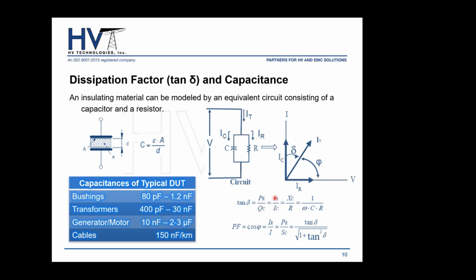Now, in power factor, basically, like I said, these values are usually very small. We're talking about, for example, in a transformer, a good transformer has 0.5% tan delta value. So we're talking about 0.005 tan delta value. So the resistive vector is usually very close to this y-axis. And so when we talk about the difference between power factor and tan delta, there really isn't a big difference. The only difference is the angle that is being chosen to evaluate.